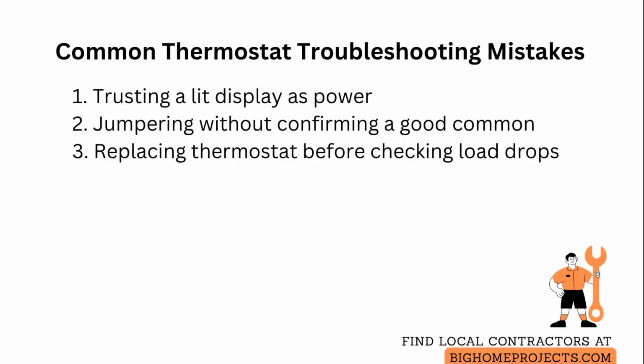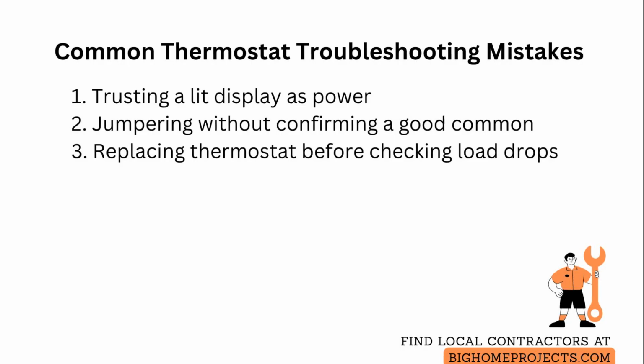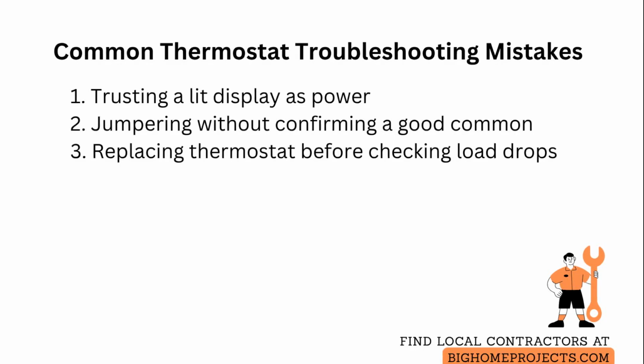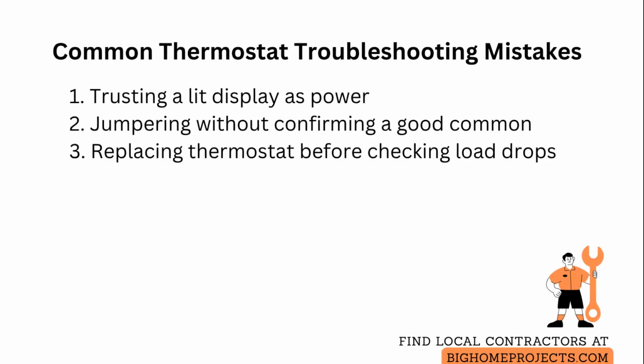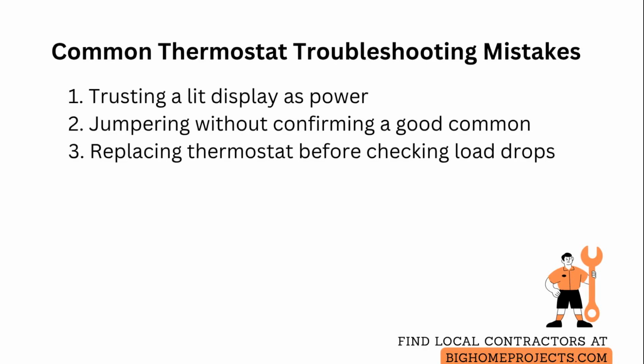if the equipment responds. The third is replacing the thermostat too soon when intermittent float switches or a weak transformer is dropping voltage under load. Watch the meter with the call engaged and look for voltage sag, then correct the cause by clearing the drain, securing the switch, or sizing and replacing the transformer.